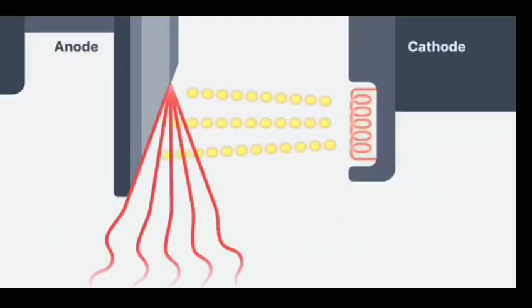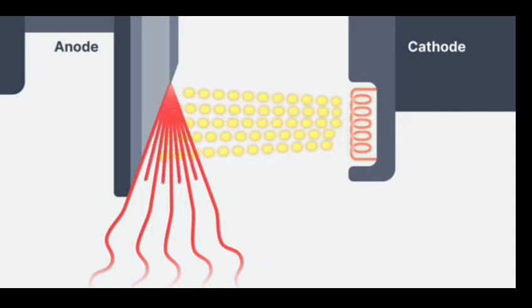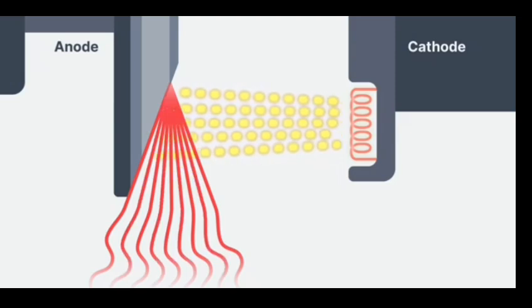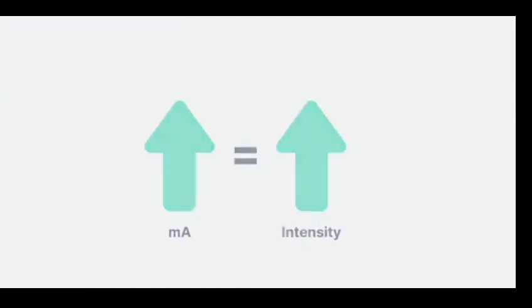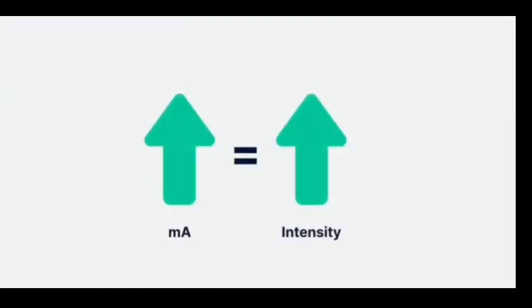The process of creating the X-ray tube current starts at the cathode filament. Setting the mA at the control panel is the primary factor controlling the amperage applied to the filament. As we increase the mA, this increases the filament amperage, which increases thermionic emission, increasing the number of electrons created, which are then available to flow across the X-ray tube and collide with the anode, creating X-rays. So tube current actually starts with thermionic emission and the filament current.